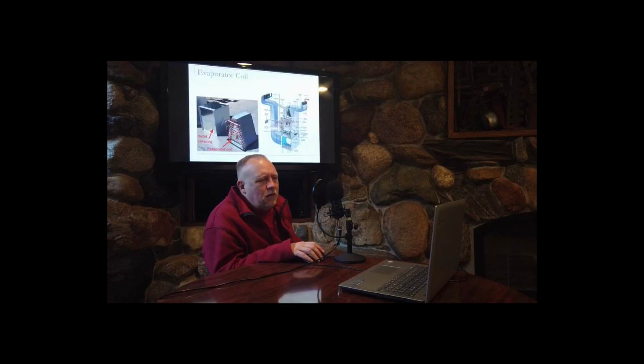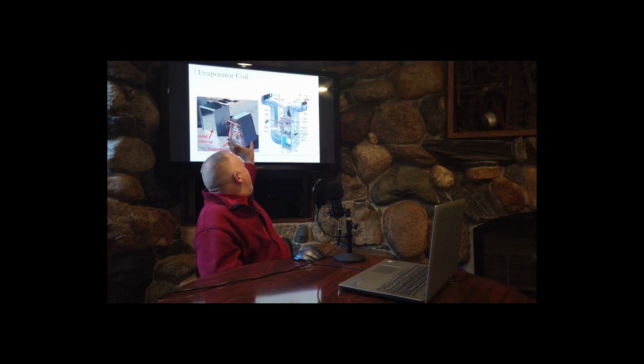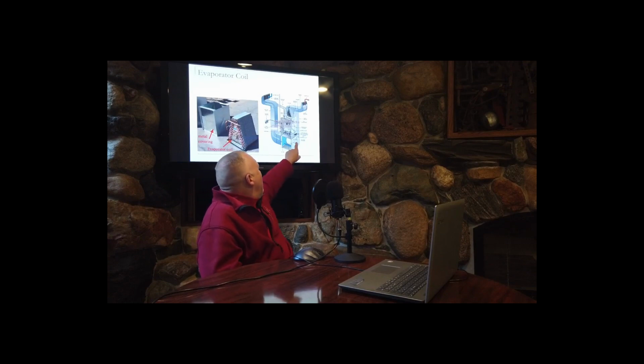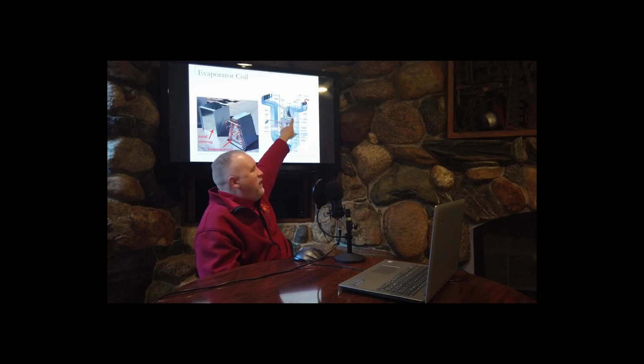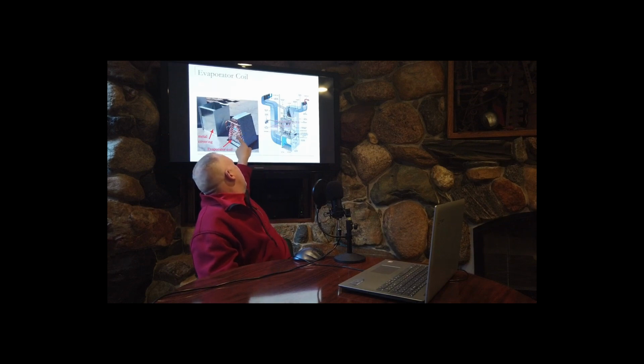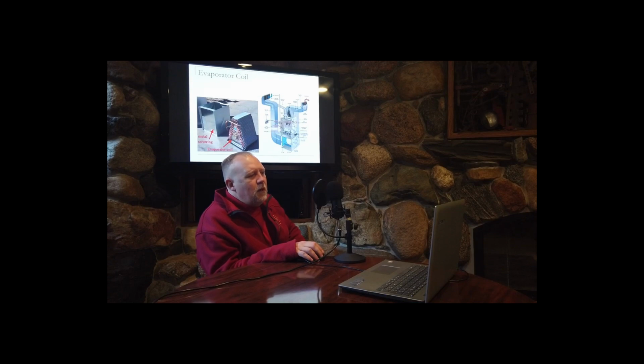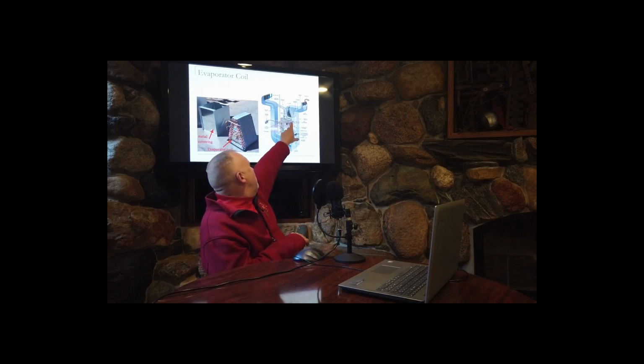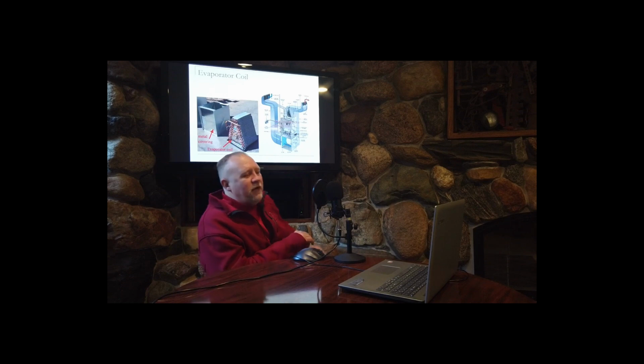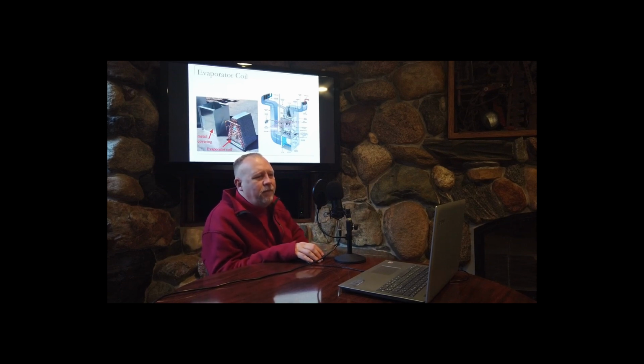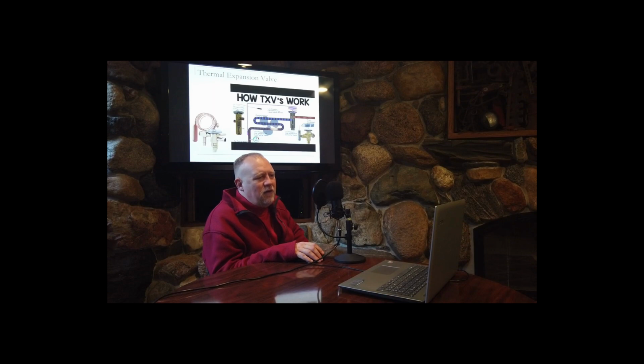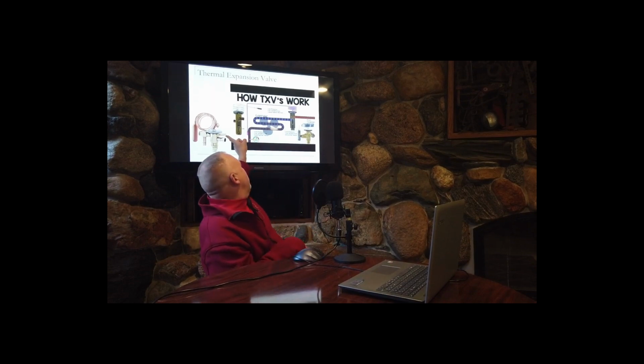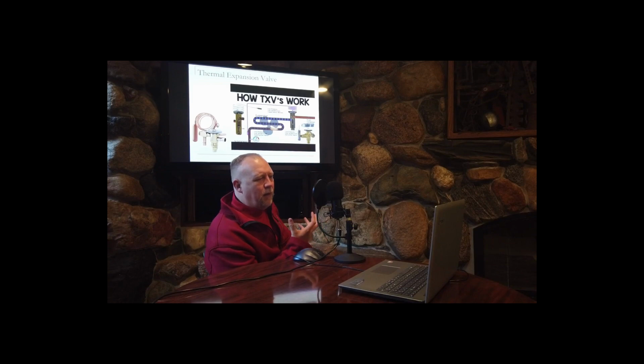That's the next picture. Here we go. Here's the evaporator coil. Here's a picture of one. Here's our furnace. It's just going to sit on top of it. Here's the evaporator coil. You can kind of see right there. The evaporator coil is going to have the thermal expansion valve inside of it. Now, you're not going to see this. This is just going to be covered by a big piece of sheet metal. That's what that metal covering is right beside it. And then inside, here is a picture of a thermal expansion valve. It's just going to be a brass control valve with copper fittings.